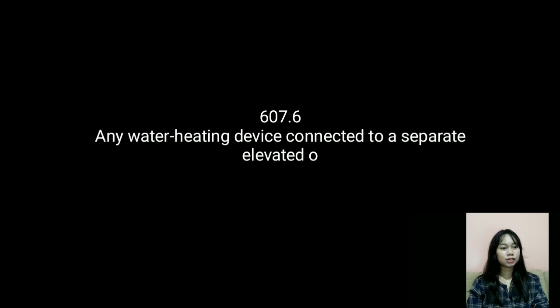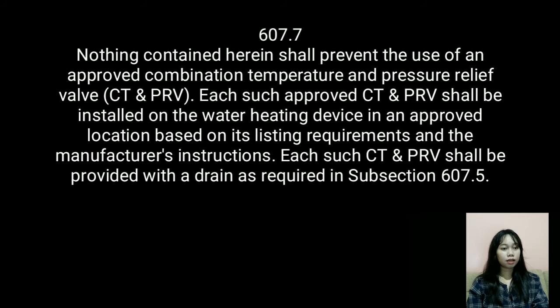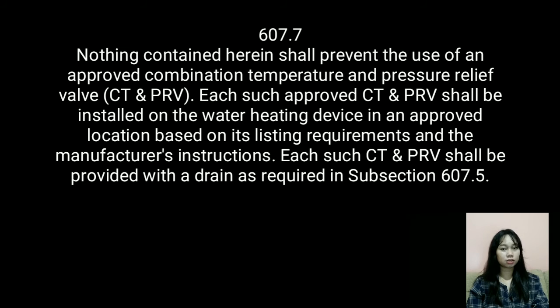Section 607.6: Any water heating device connected to a separate elevated or pressure-type storage tank and having valves between said heater and tank shall be provided with an approved water pressure relief valve. Section 607.7: Nothing contained herein shall prevent the use of an approved combination temperature and pressure relief valve (CT&PRV). Each such approved CT&PRV shall be installed on the water heating device in an approved location based on its listing requirements and the manufacturer's instructions, and shall be provided with a drain as required in Section 607.5.